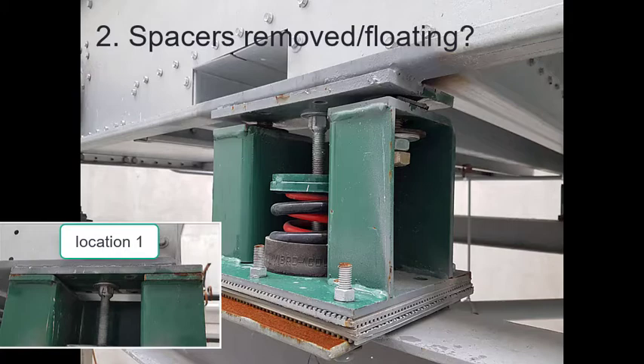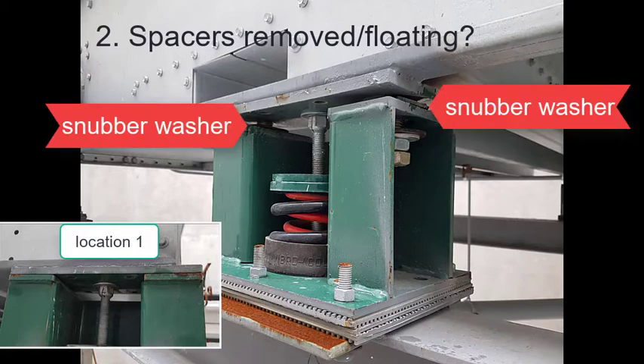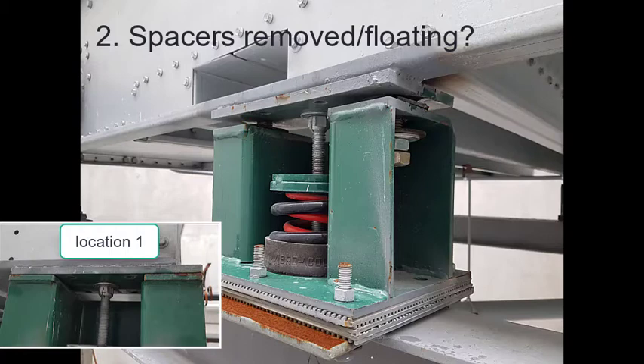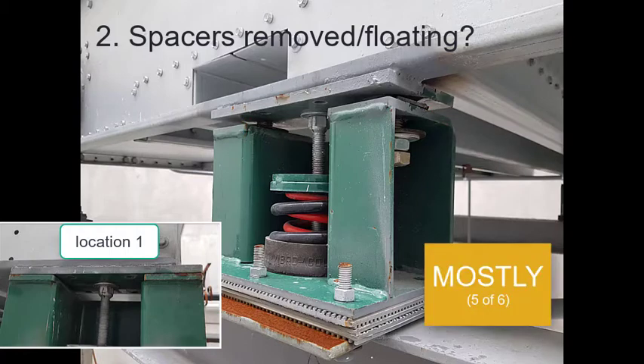This could be a problem that may create a vibration isolation short circuit path where the vibrations from the equipment go through the side stanchions instead of into the spring. It was difficult to tell for sure, but I think the snubber washers were doing their job to prevent metal-to-metal contact, which could have caused further structure-borne noise problems. So the answer to this question goes in the mostly okay category.